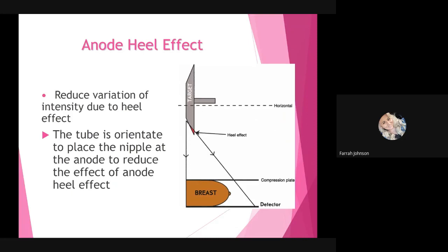So then going back to our anode heel effect, we know that the anode heel effect is going to help reduce variation of intensity, meaning that anytime you have an X-ray beam, your X-ray beam is always going to have a lower energy on the anode side. And that is because this target material is going to absorb part of your X-ray beam. So what gets emitted ends up being a little bit smaller energy or decreased energy as compared to the cathode side. So the tube is orientated to place the nipple at the anode to reduce the effect of anode heel effect and maximize homogeneous density across the breast.